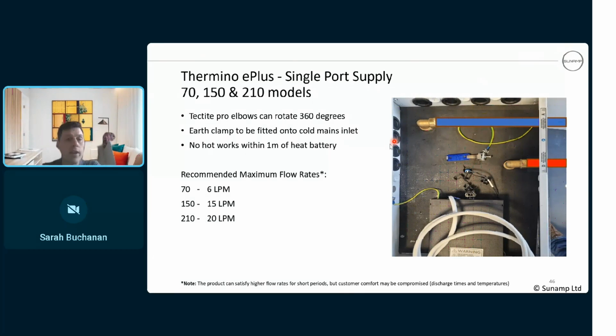You've got your recommended maximum flow rates. For the 70, we recommend 6 litres per minute, the 150 is 15, the 210 is 20. If you're fitting a Thermino 70 and you've got 8 litres per minute, it's still going to work. Again, we've got the note here at the bottom: it can work with higher flow rates. It just means that your capacity might be slightly less, because the water's running faster, so there's more heat exchange going on for that size of unit. So it's just something to bear in mind.